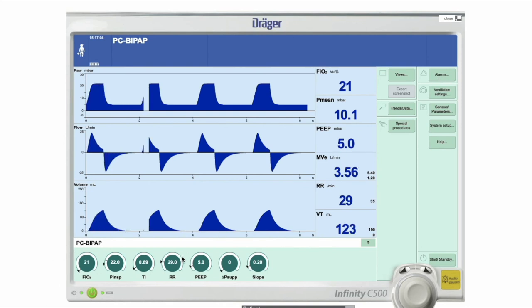Right, so that's a look at the alarm. We've already looked at the settings here. So now we should have a look at the display. So what's displayed when the ventilator goes on? Is whatever you want displayed. So as default, what we have are the pressure versus time, flow versus time, and volume versus time kind of information, and these are very good to look at. As soon as you put a patient on the ventilator, they're the things that will give you the initial information on whether your patient's ventilating properly.